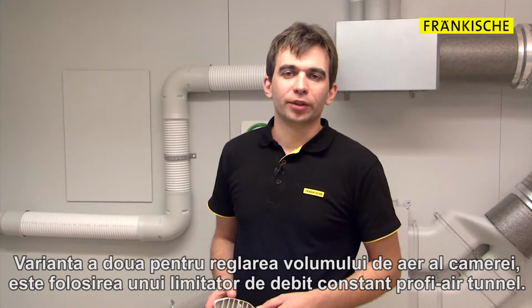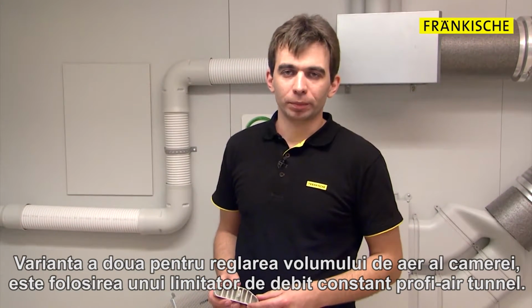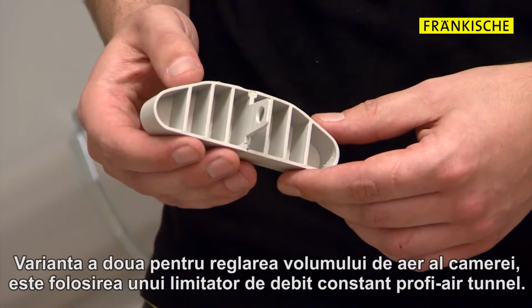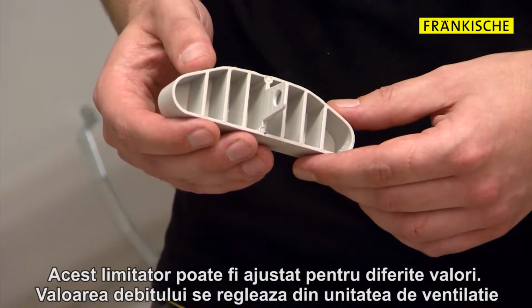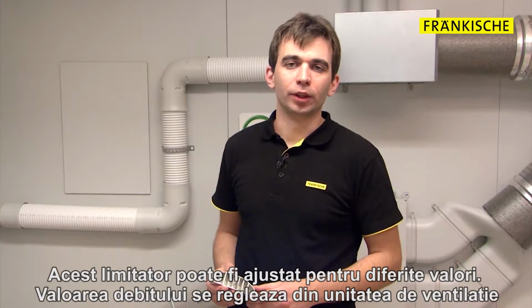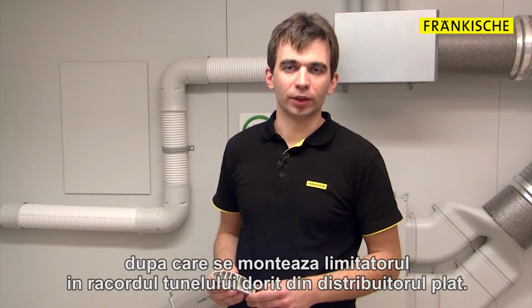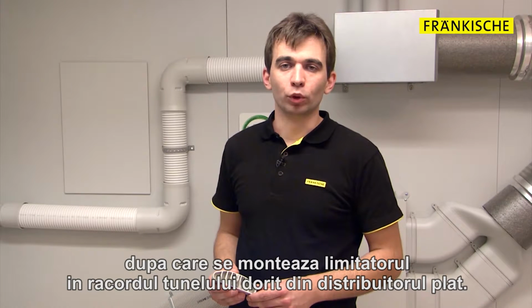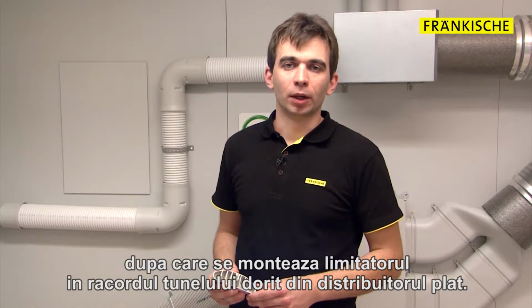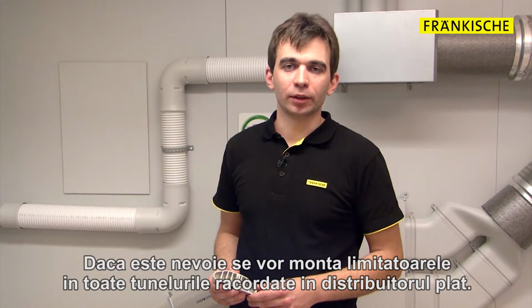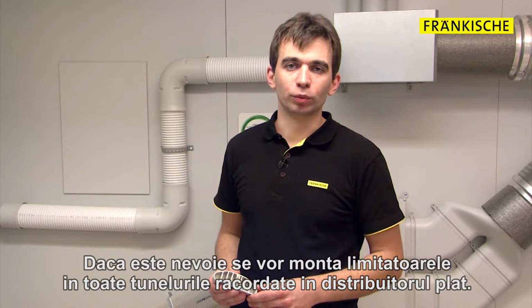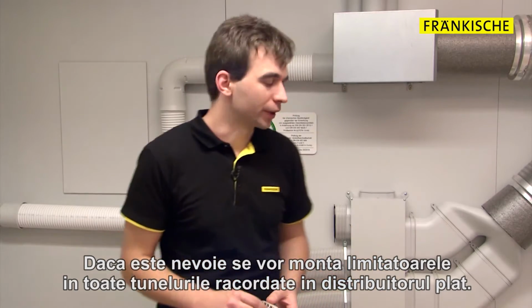The second option for adjusting the room air volume flow rates is using a tunnel airflow restrictor. This restrictor is used when non-adjustable valves or grills have been installed. As described in the first option, the total air volume flow rate must first be adjusted at the ventilation unit. Then the tunnel airflow restrictor is installed in the flat manifold in order to restrict the individual air volume flows.